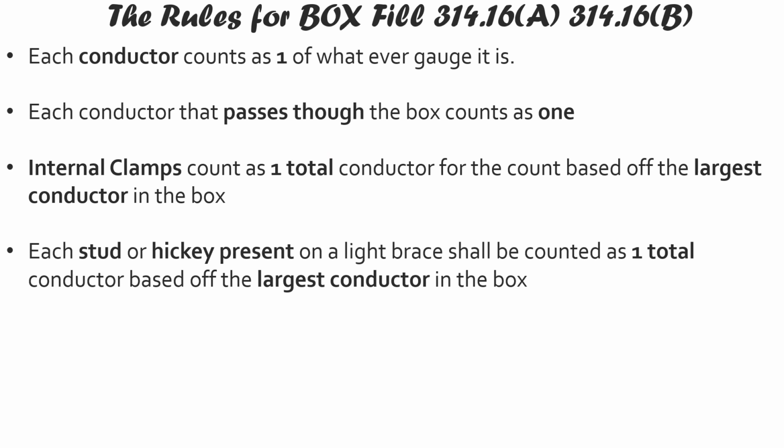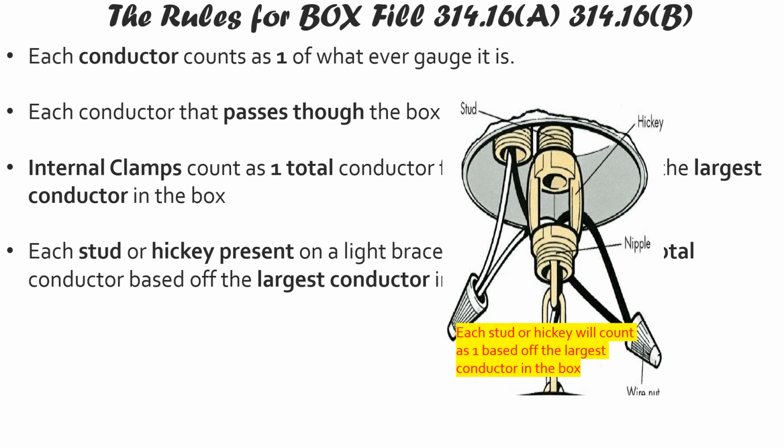Next, each stud or hickey that is present in the box shall count as one total based off the largest conductor that's in the box. Now, these are really old words, probably from the 30s if I had to imagine, but they still use them on examinations today. And this is what we're talking about. Imagine that we're hanging a chandelier. This we would call the stud or the nipple. Or, this would be the nipple. But they're calling this the stud and this a hickey.